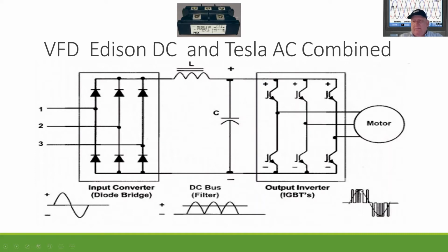pulse width modulated power surges towards the motor winding. And this varies. Then we can control how far apart the frequency is. Instead of being 60 cycles a second, we can go clear out to 120, which will make it faster, or we can bring it all the way down to like 10 cycles, 10 hertz. Hertz and cycles are the same thing.